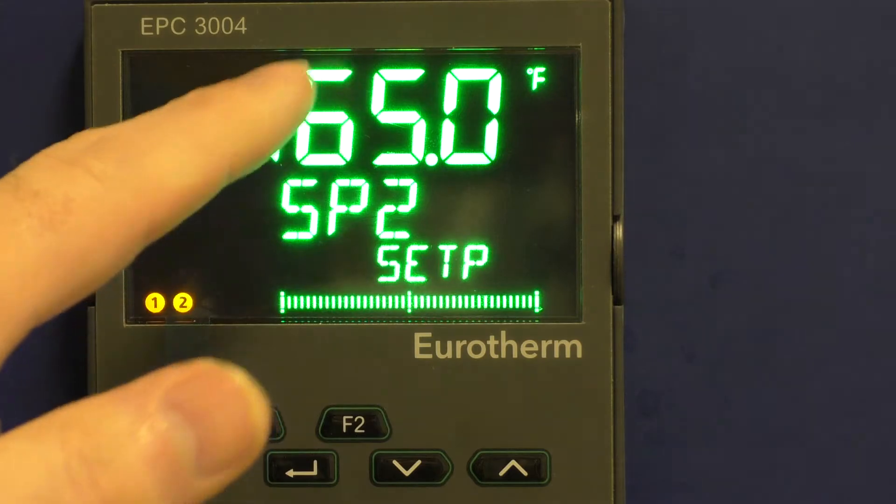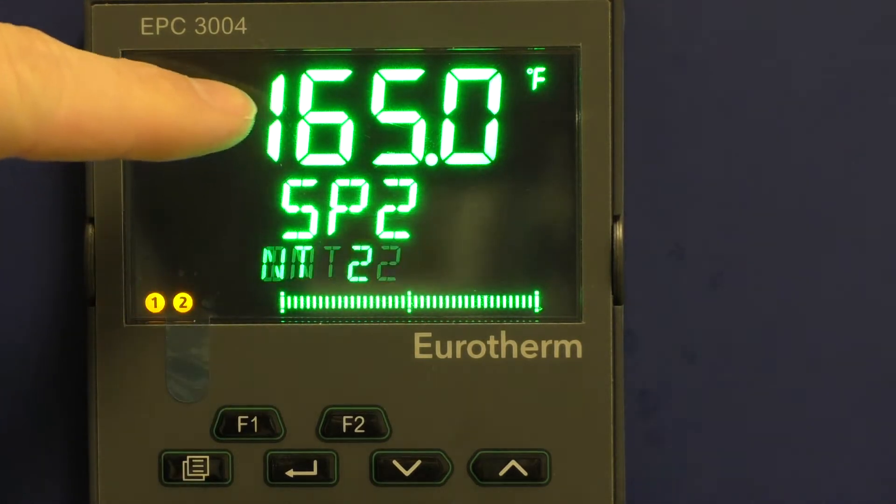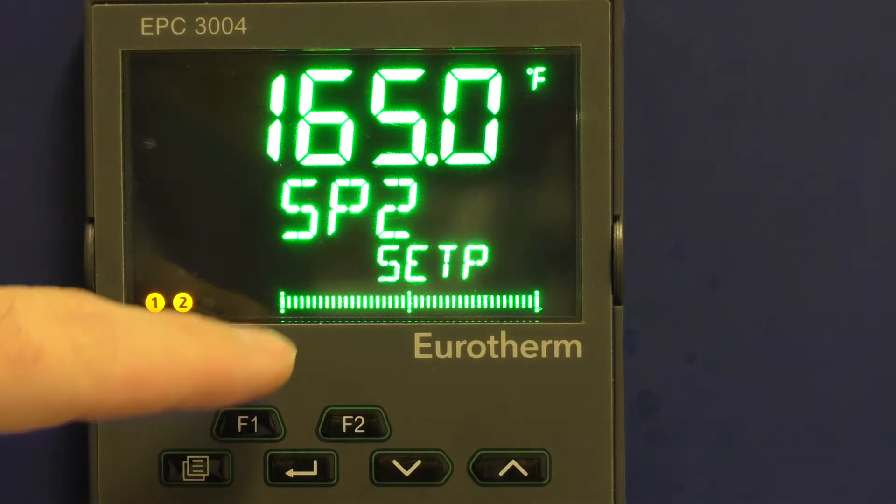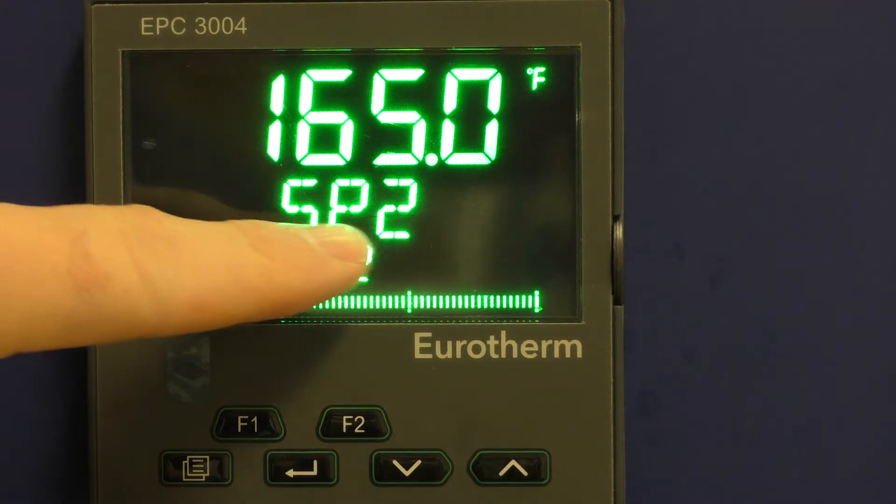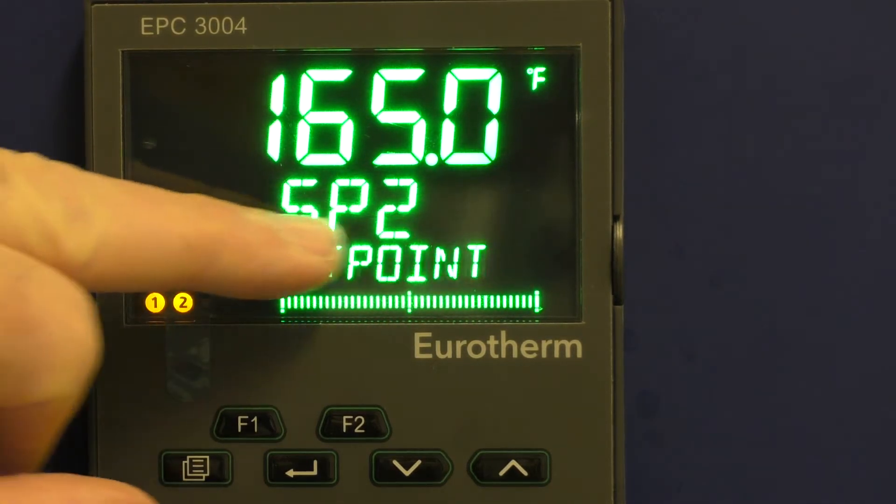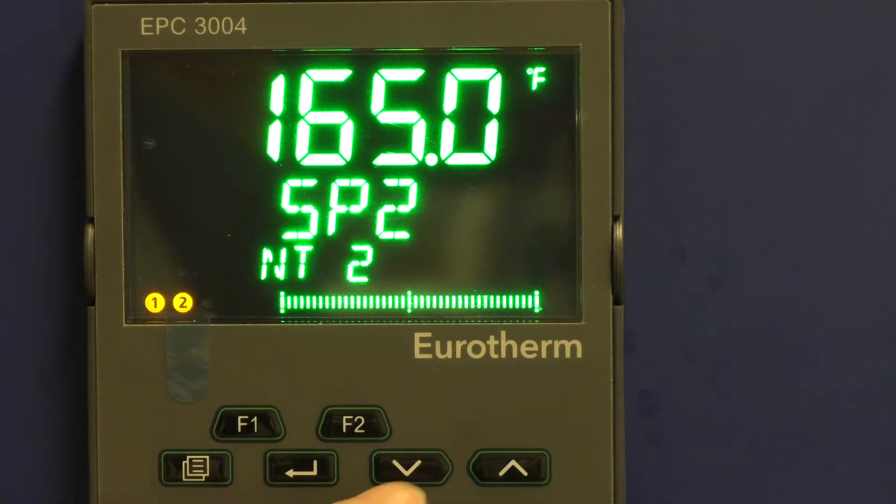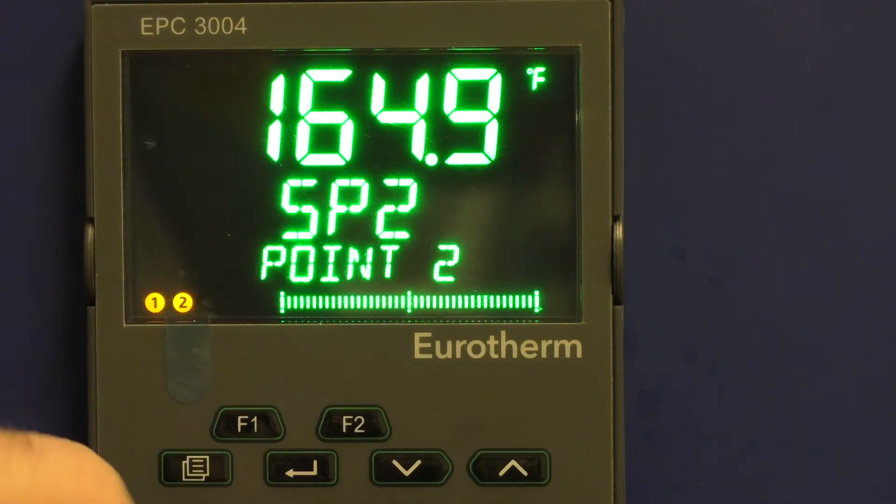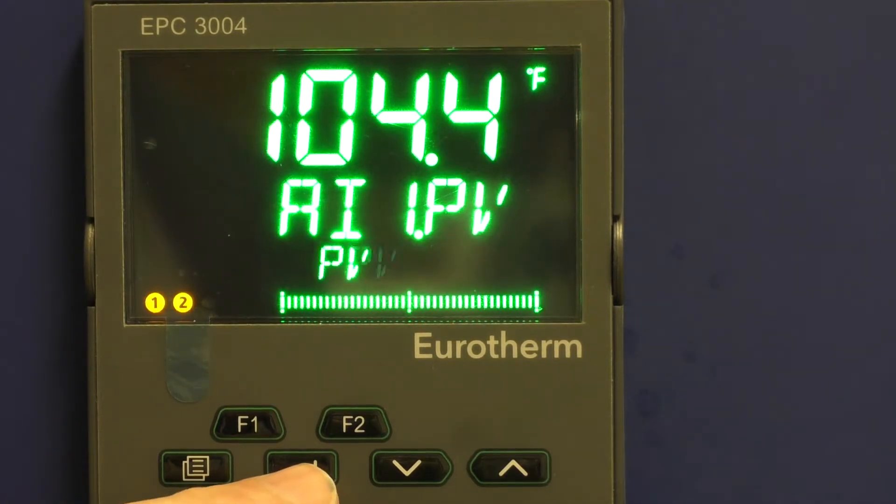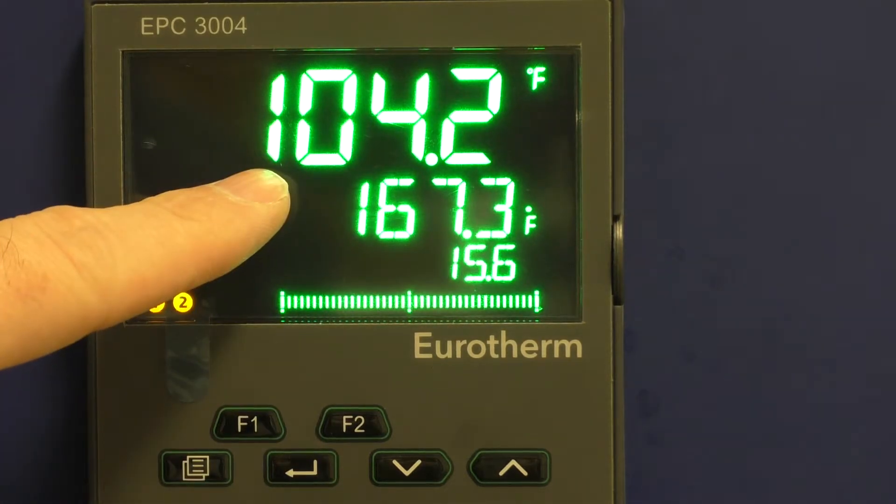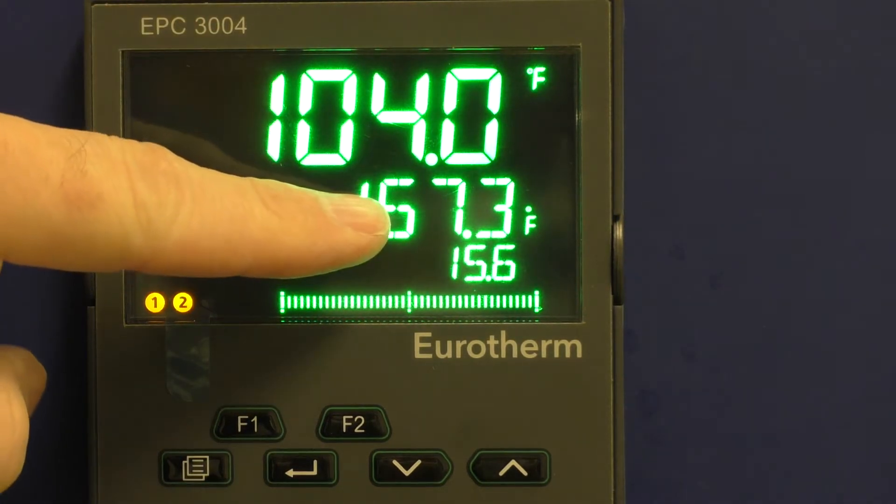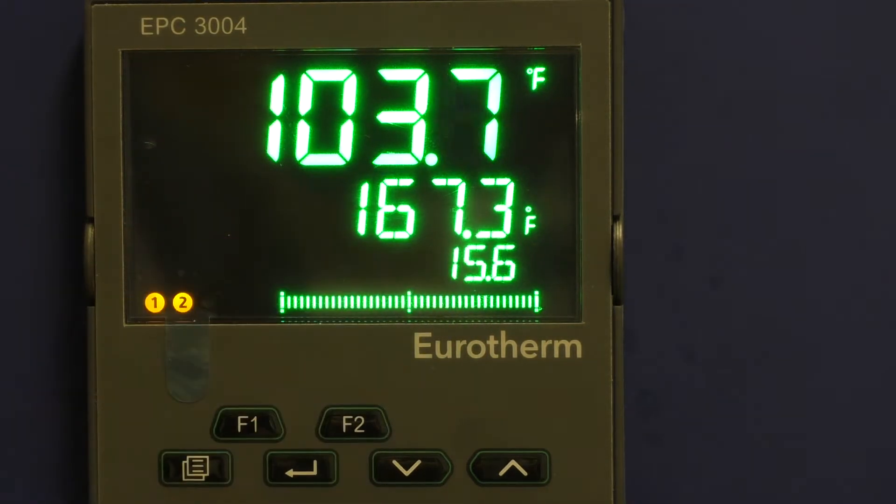Now I can go through and preset my timer temperature if I want by scrolling through here, getting to SP2. This is always in reference to the timer, and I can change that to 165, to 164.9, and then you can hit the return key until you get back to the main screen. So again, internal temperature, set point that it's trying to use at the moment, and internal humidity.